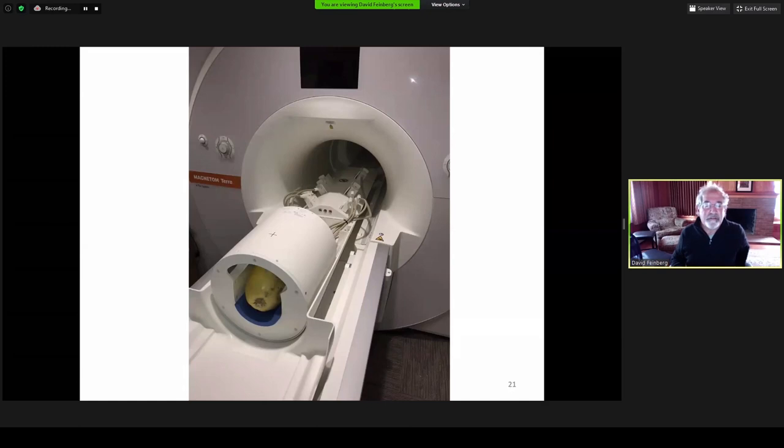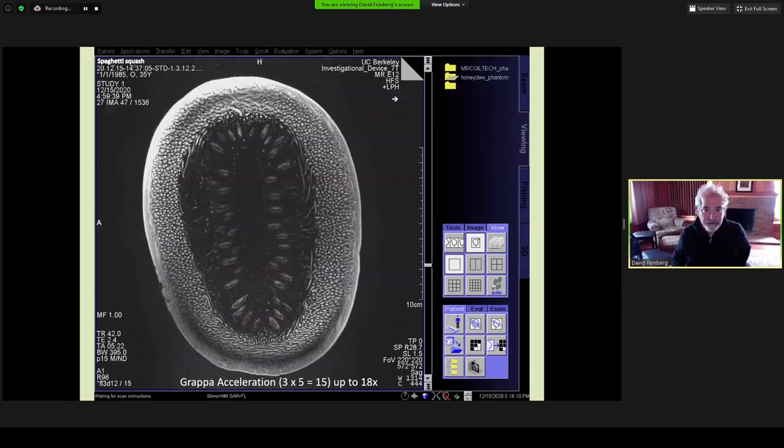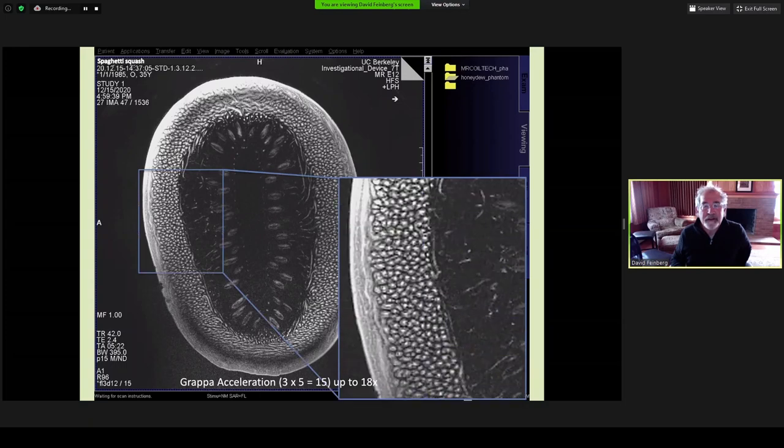We tested on different size melons and larger squash that are about the size of the head. Here you see a spaghetti squash that we imaged. Very pleasing high-resolution images. The gradients allowed a slightly earlier TE, but what was most interesting was the acceleration factors that we could go up to as high as 18 on these initial tests, which is far higher than we could ever achieve on a 32-channel coil.